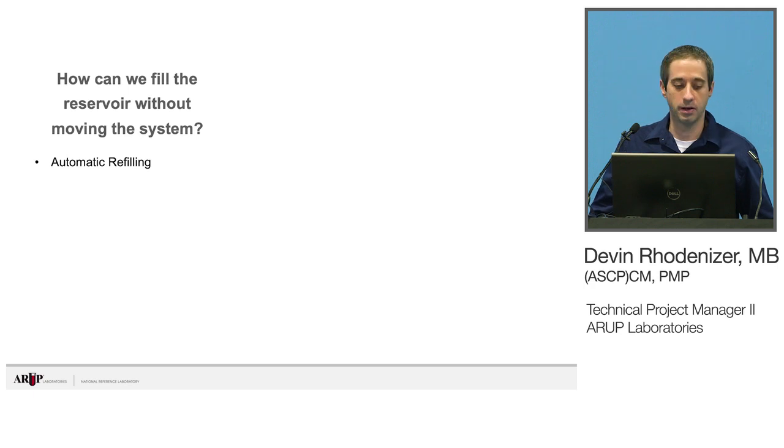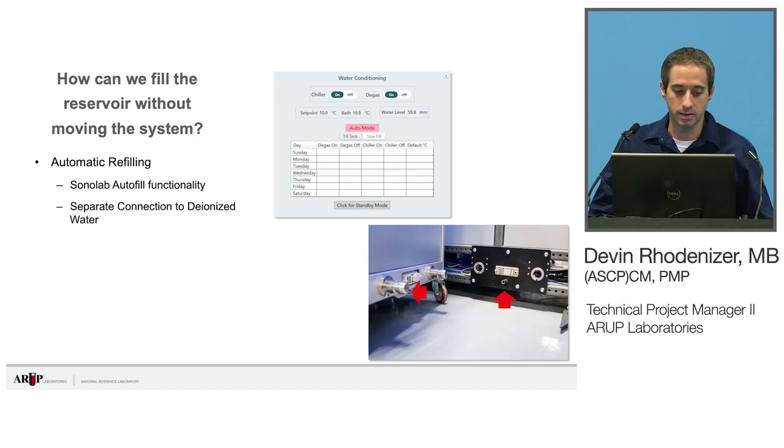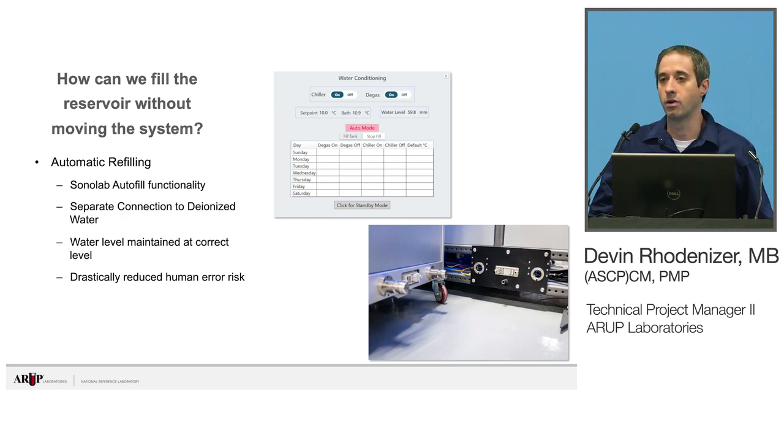Kovaris has added an automatic refilling function to Sonolab — an autofill mode — so as long as a water line is connected, it'll constantly refill the system. We can put the system in without any water, and about 45 minutes later it's full and degassing and ready to go. On our side, we added a separate connector to the deionized water system — kept separate from the docking mechanism because water and electricity don't mix. This always maintains the water level at the correct level and drastically reduces human errors, because now there's no one eyeballing whether the water level is right.